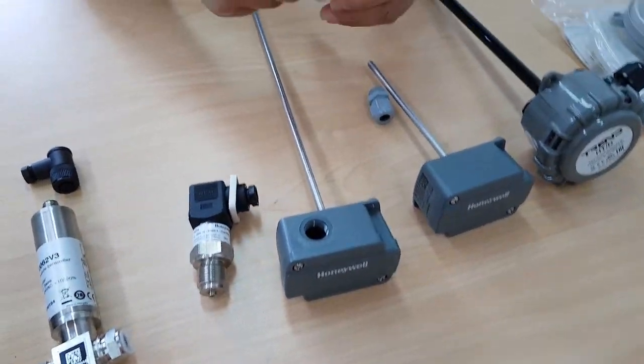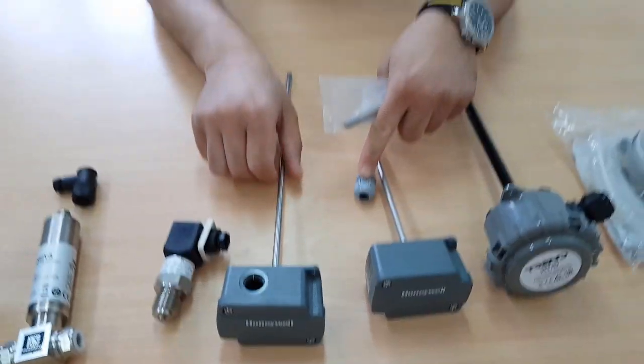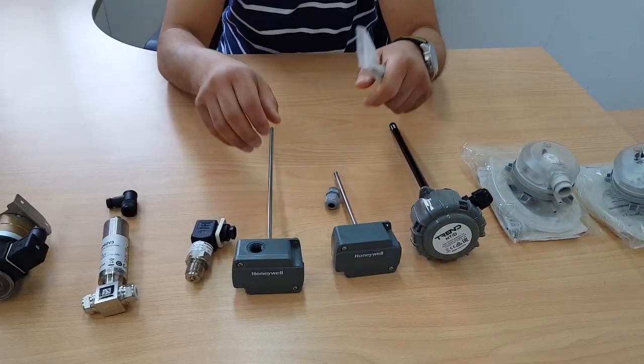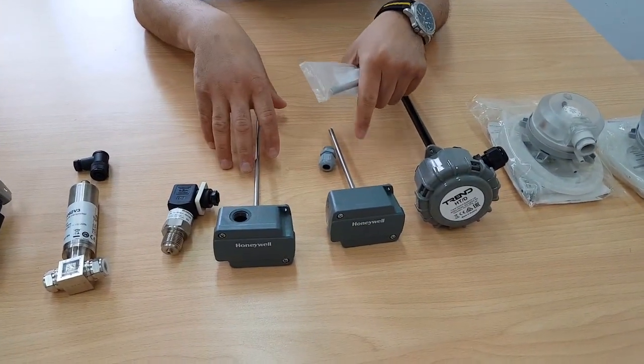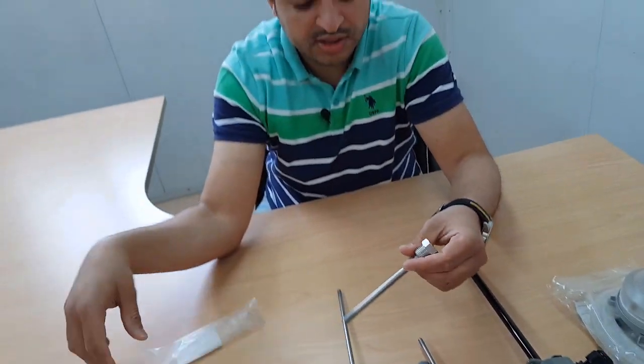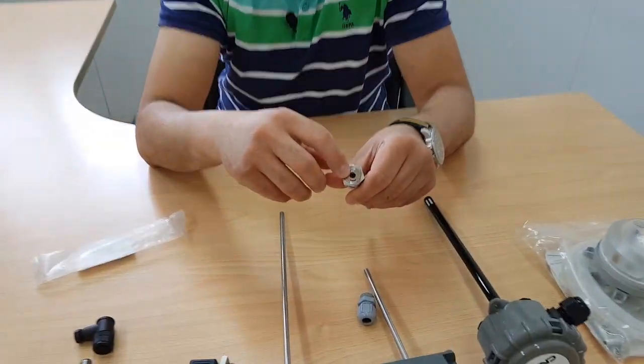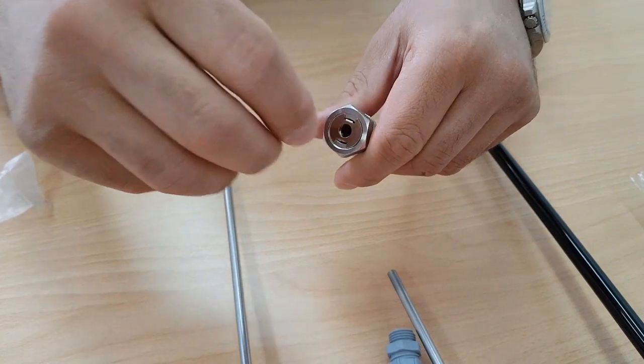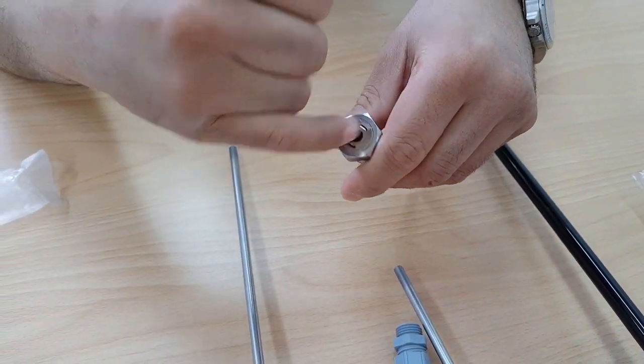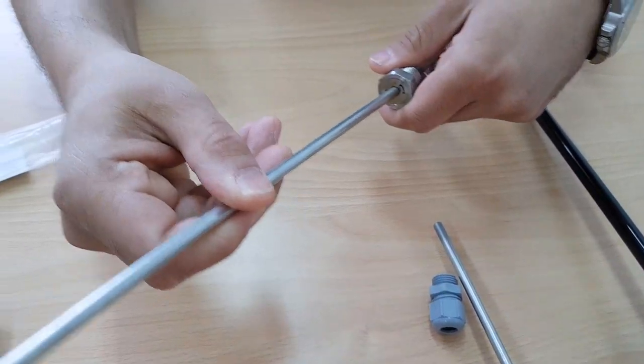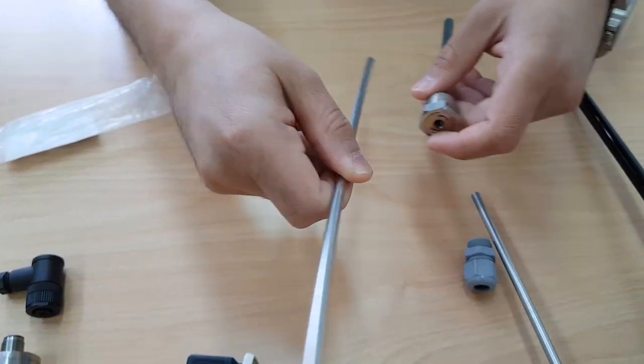Without using an immersion well, it will be used only with the HVAC duct. But if we need to use them with water, we shall use an immersion well. So we'll remove this nut here and insert the probe inside the immersion well, to allow using it inside the HVAC pipes.